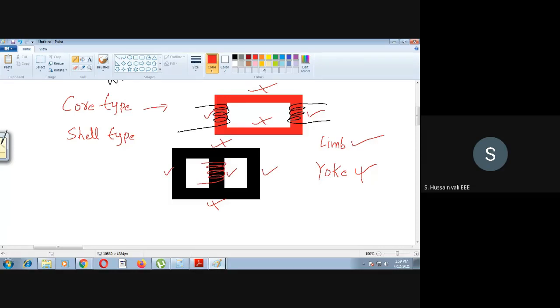On the central limb itself you have both the primary and secondary windings - blue color and red color, both drawn here - so the primary winding and secondary winding are on the same limb. Whereas in the core type transformer, part of the winding is on one side and part on the other side, in the shell type, the total windings are found only on the central limb. So this is a shell type transformer, and this is a core type transformer.